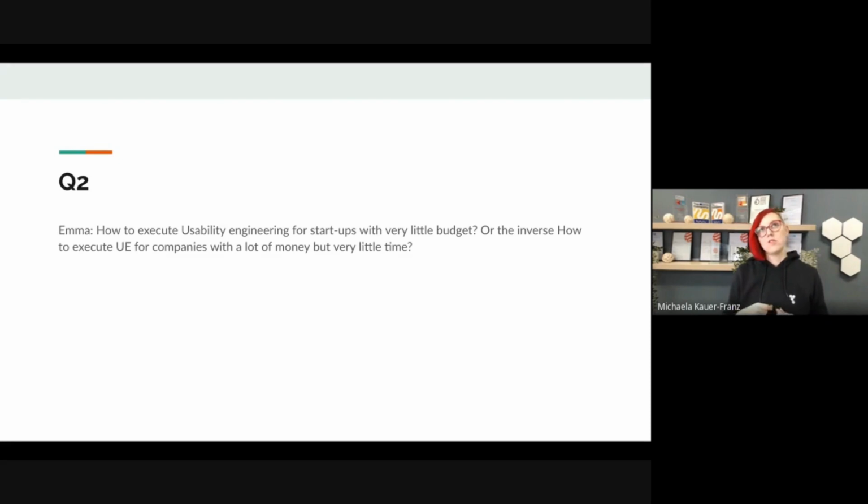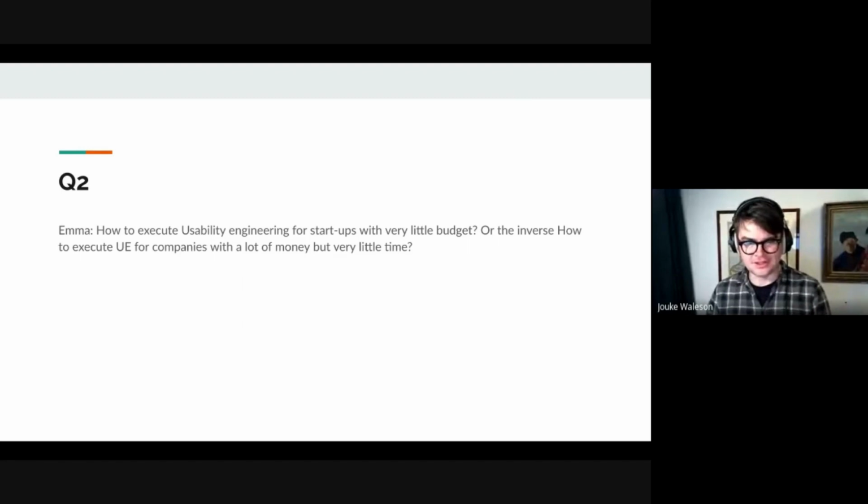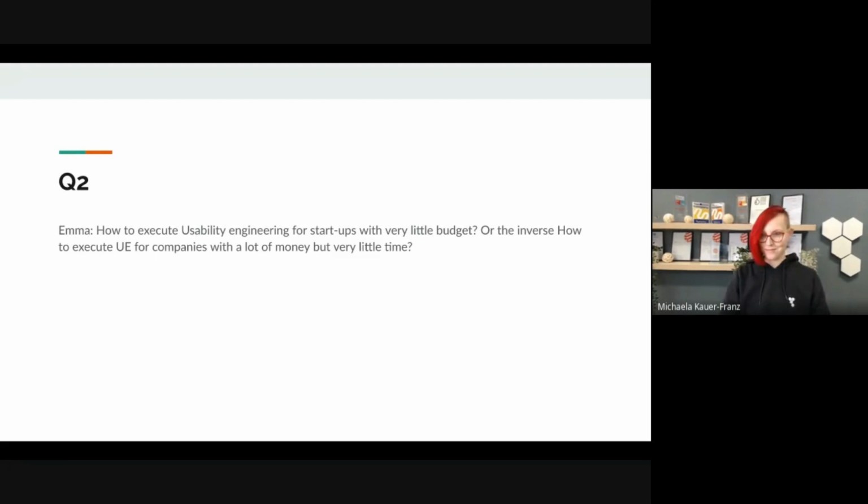And in general, leaving the time aspect out, if you have the capacity to invest into usability engineering, the most important part is the only non-mandatory part in the process. It's the formative testing. So go for the formative testing, and this will save you a lot of money. It will bring you market share. It will improve everything that you do. And it will be actually the only thing that is relevant for your device. Everything else is just paper for the actual usability and the UX of your device. So yeah. Start very early with formative testing. Yes. Okay.